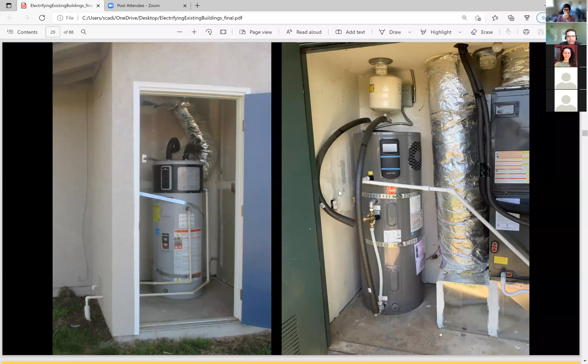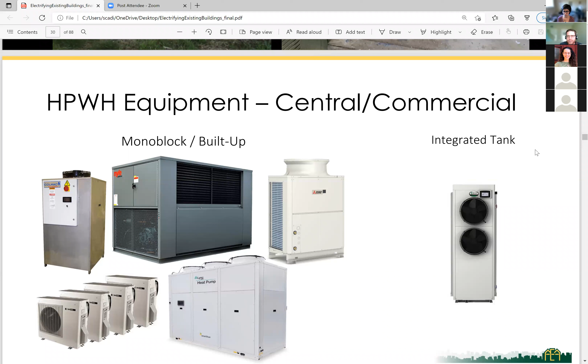For larger multifamily buildings, many have one big hot water plant for the whole building, or commercial facilities with a large hot water boiler for domestic hot water. There are central commercial heat pump water heating systems that can replace those central gas water heaters. They make integrated tanks, like on the right, where a very large heat pump connects to the tank—a great application for smaller multifamily buildings, maybe under 20 units, and also for restaurants. Not only does it create enough hot water for the restaurant's usage, but installed in the commercial kitchen it also provides free air conditioning, since those kitchens get pretty hot. On the left you can see commercial-size heat pump water heaters; many can be sited outside, like on a roof, paired with storage tanks.